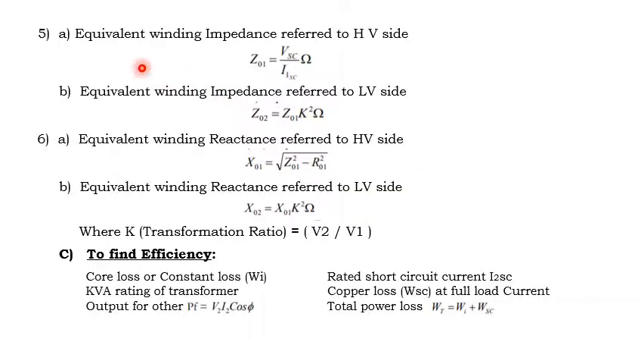Then the equivalent winding impedance referred to the HV side, that is Z01. Again this is a simple formula, calculated by VSC by ISC. Then the equivalent winding impedance referred to the LV side can be calculated by Z02 is equal to Z01 K square ohm. Again K is the transformation ratio. Here you can consider the transformation ratio as the voltage ratio, that is V2 divided by V1. Then substitute that value and multiply by Z01, and you will get the equivalent winding impedance referred to the LV side.